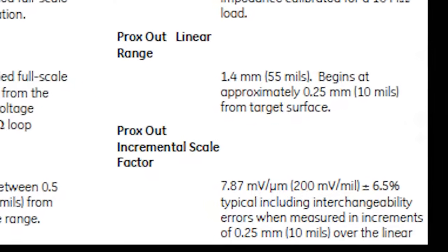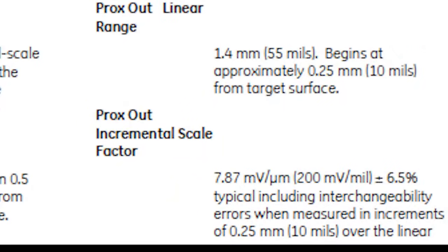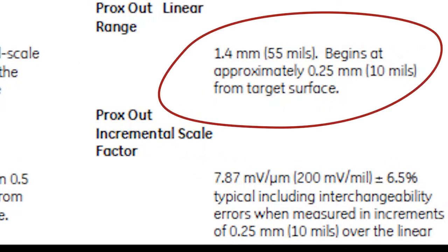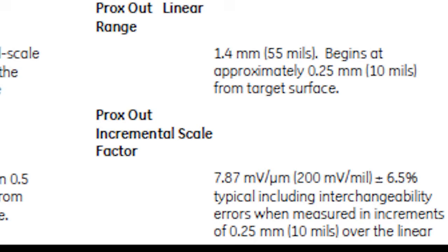First, identify the range of linearity. This specific probe has a range of fifty-five thousandths, starting at ten thousandths from the end of the probe. Most proximity probes have a response rate of 200 millivolt for every mil of travel. This means that every ten mils of travel will produce two volts of change.